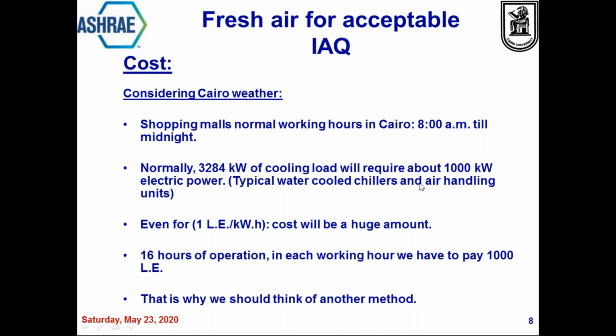The load will require about 1,000 kilowatts of electric power, 1 megawatt, typically if we use a water-cooled chiller and air handling units. Even at a low tariff of 1 Egyptian pound per kilowatt hour, the cost will be huge. By the way, $1 is about 16 Egyptian pounds. If we consider 16 hours of operation in such working conditions, then we pay about 1,000 Egyptian pounds, and this is way too much than it should be. Now, we have to think about another way.